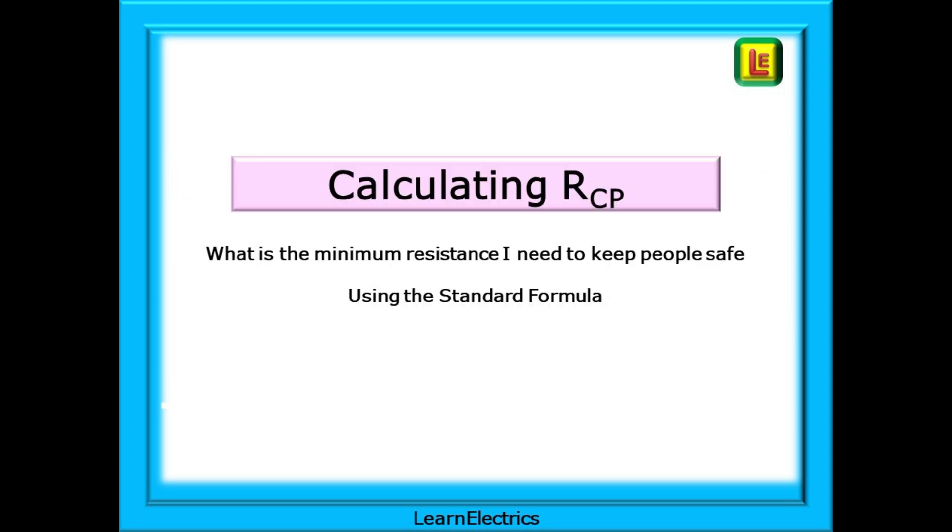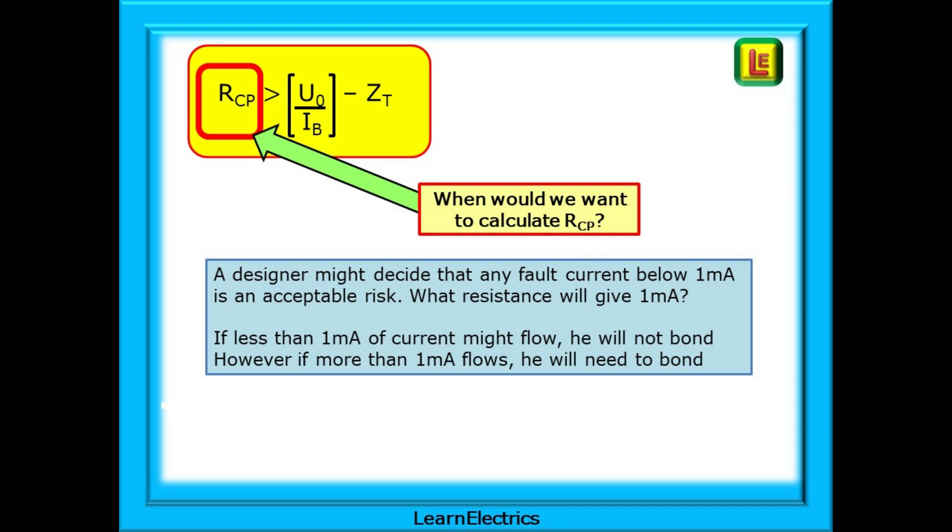So what is the minimum resistance needed between conductive parts and the installation's main earth terminal to keep people safe? For this, we can use a standard formula as shown in Guidance Note 8. When would we want to calculate RCP? Let's look.